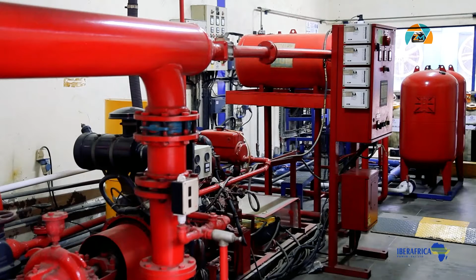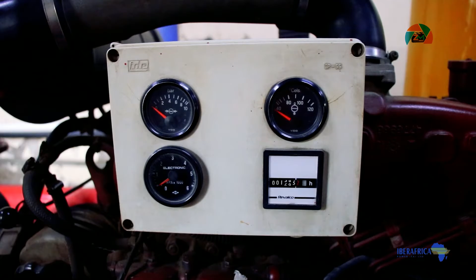This is a very important room as far as fire safety is concerned, because this is where we have our fire pumps. In case of fire, we need the pumps to build enough pressure to use water to extinguish it. Besides me is the fire electric pump panel. We have two pumps in parallel: in the event that one pump is electrically energized, the other, a fuel-fired pump, is used if we don't have electricity. This system is always pressurized so that in case of fire, we can readily deploy high pressurized water to fight it.